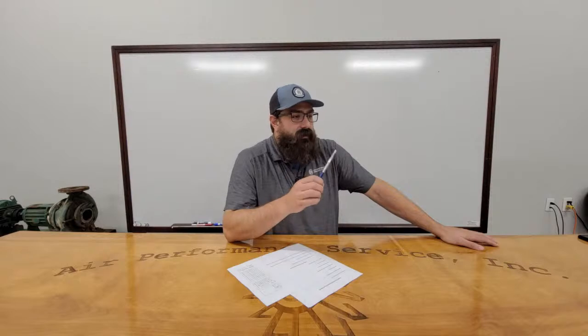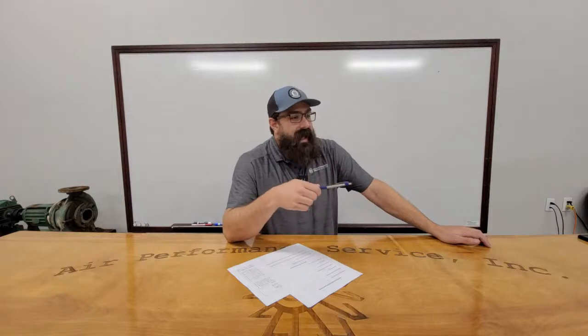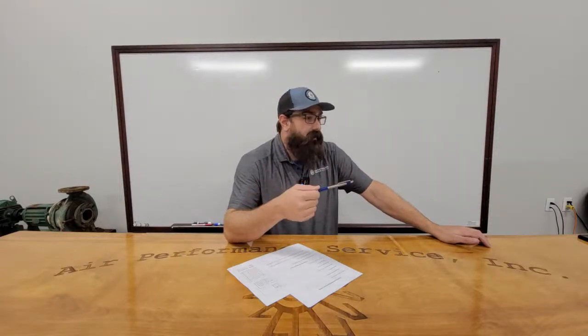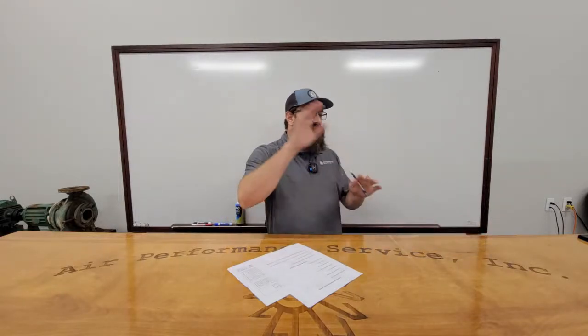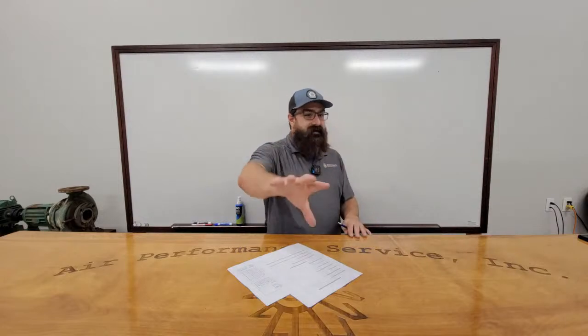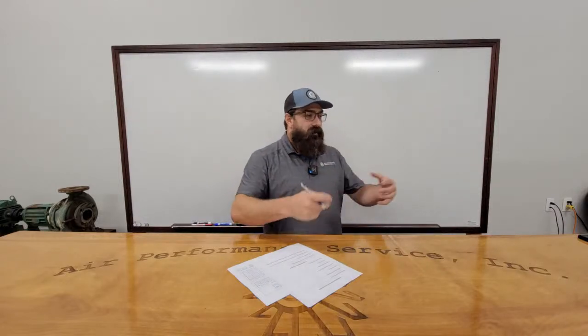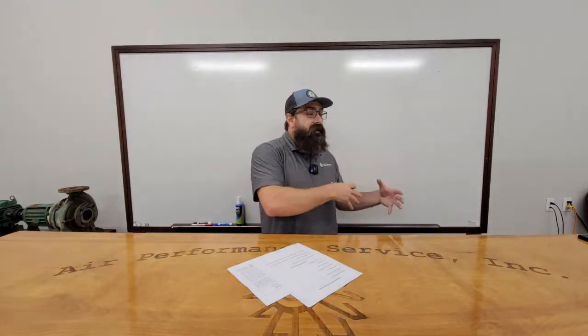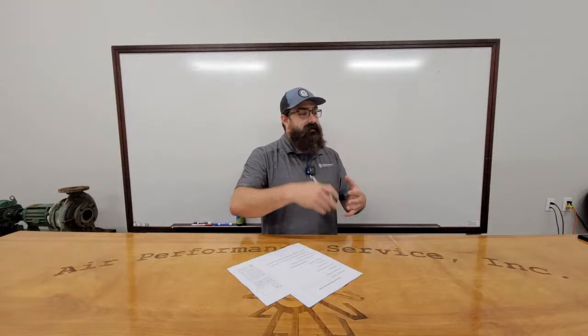Well, I mean, I see the duct heater, because if it was an aftermarket duct heater installed and then they use one of those Penn controllers, those are made by Penn. Yeah. JCI rebrands them, a couple other companies. And then that would control the heater, like the heat kit itself. So it would have its own set point on the Penn thing with the space temp sensor in the space. Okay. The water source heat pump is controlling the cooling side of things, and then the Penn is controlling the heating side of things. Right.